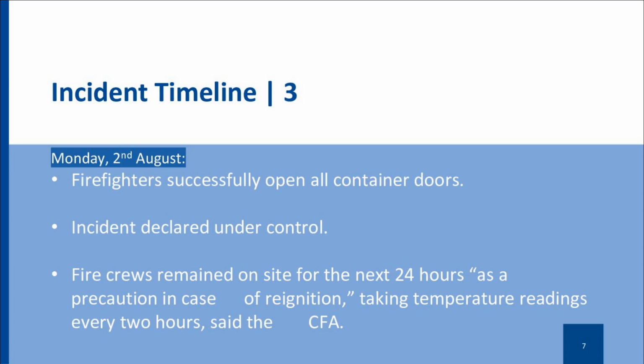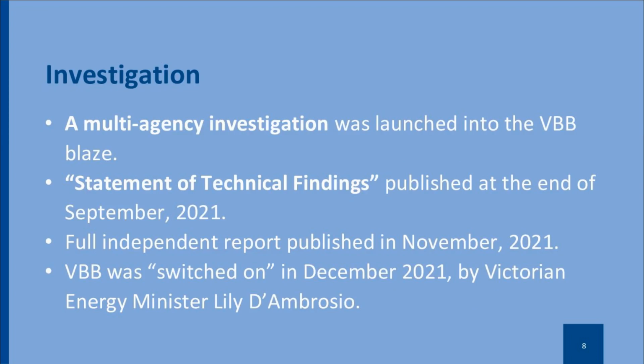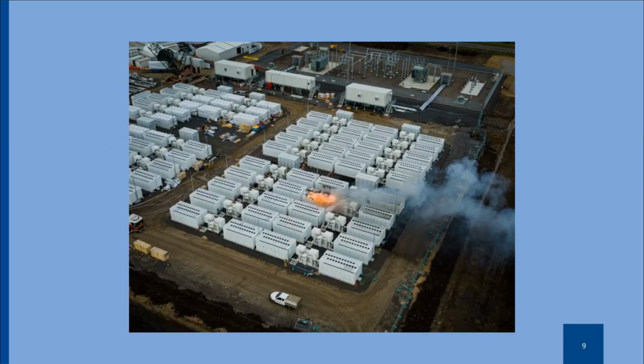The findings showed the most likely root cause of the incident was a leak within the megapack cooling system, which caused a short circuit, leading to a fire and a thermal runaway event, which then led to the adjacent fire in the next megapack. As you can see in this photo, the megapacks are about double the size of a ute, so you want to make sure you get it under control pretty quickly.